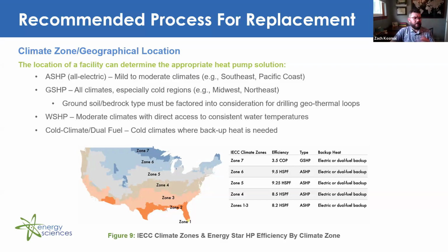As previously mentioned, as your outdoor temperature drops, the heat pump efficiency decreases. So for locations with moderate to extreme winters, with consistent outside air temperatures below 20 degrees Fahrenheit, Michigan would be a great example of that, a traditional all-electric heat pump may not be a viable option, depending on the application. Rather, a dual fuel or cold climate heat pump may be more suitable.